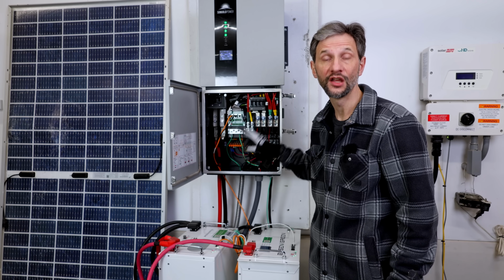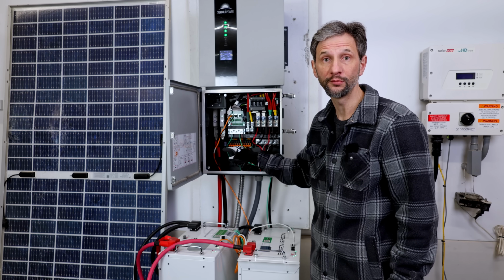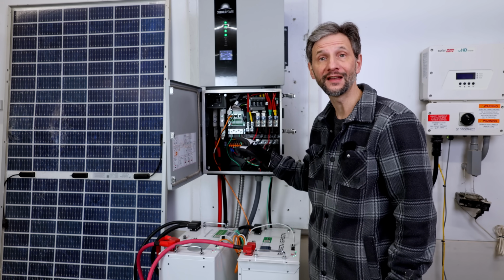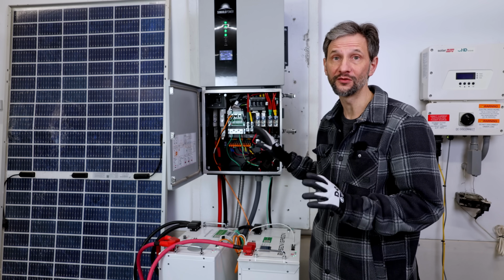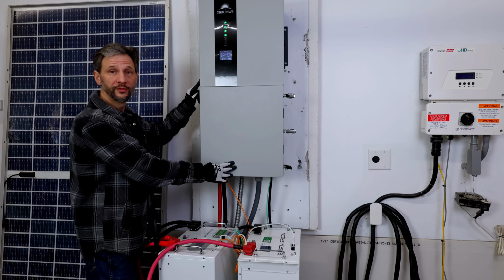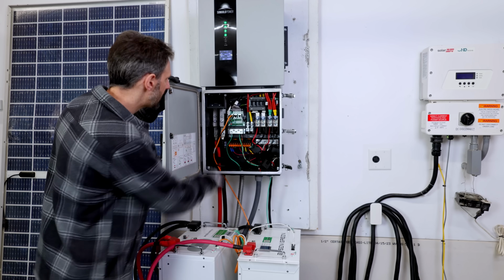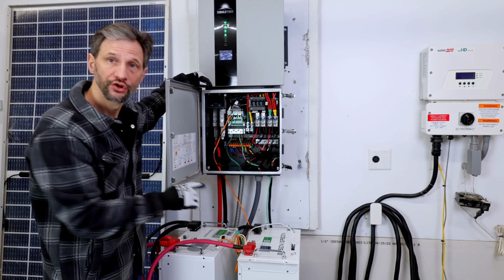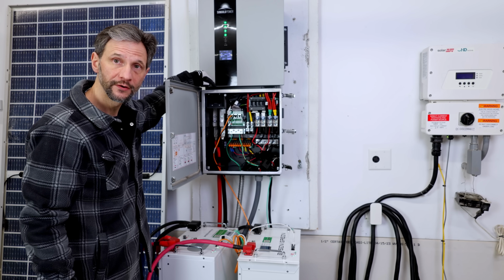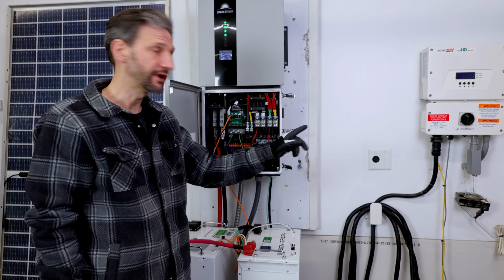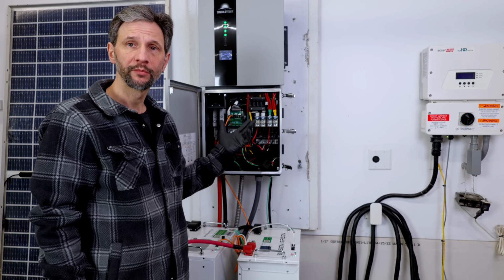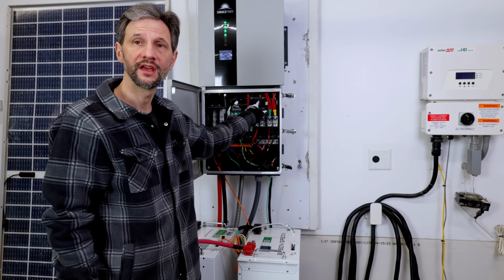With all the connections made, double check the polarity on your solar inputs at the subpanel and at the inverter before commissioning the unit. Startup is easy: turn on the PV, turn on the DC batteries and the DC battery breaker, turn on the batteries, then turn on the DC breaker, then turn on the breaker for AC input. Once it powers up, you can turn on the AC output.